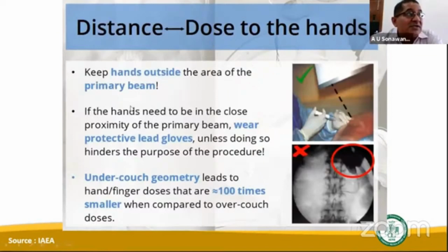This is very important, because if we don't wear the gloves, then definitely your extremities get irradiated. If the hands need to be in close proximity, then wear protective lead goggles and lead gloves, unless they hinder the purpose of the procedure. Suppose the visibility is not clear because of the lead gloves and you are using an automatic exposure control device, then the current will shoot up because of the low signal, and exposure will be more. So we have to be very careful even in using lead gloves. Whenever it is very necessary, use them, and generally avoid the hands in the primary beam.